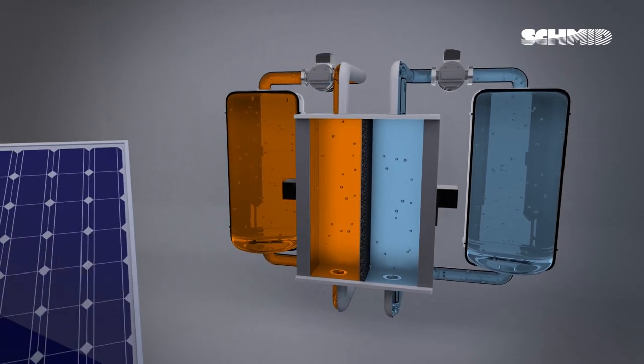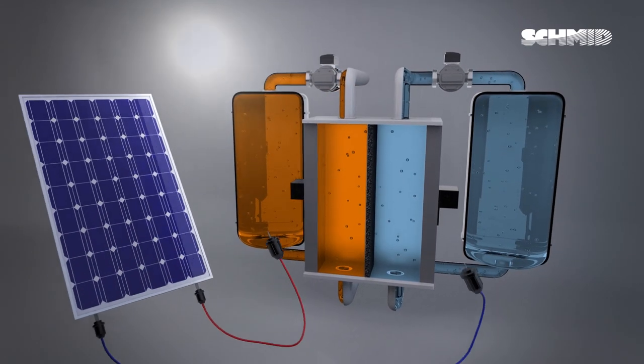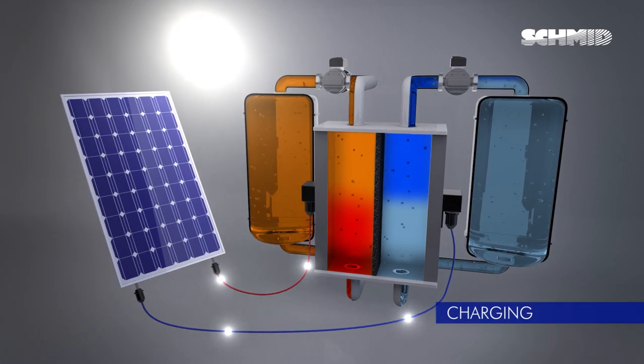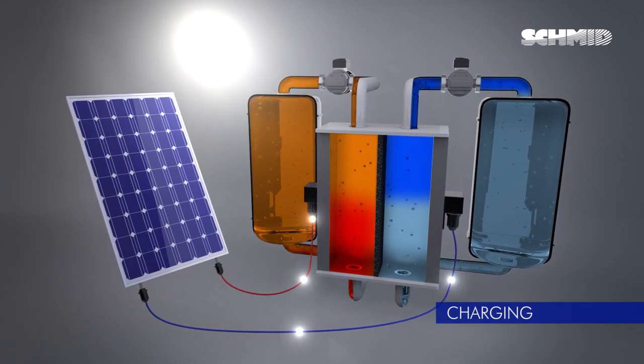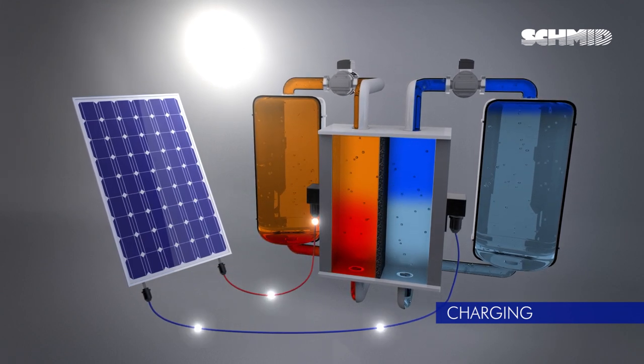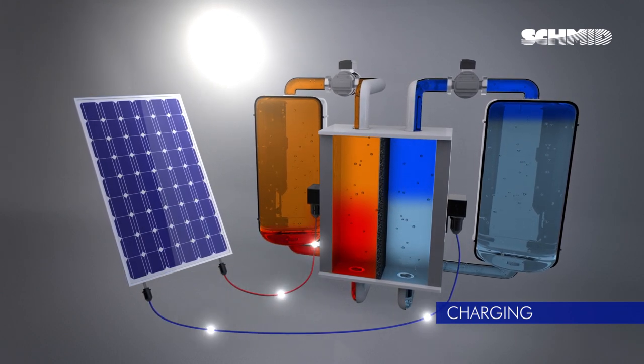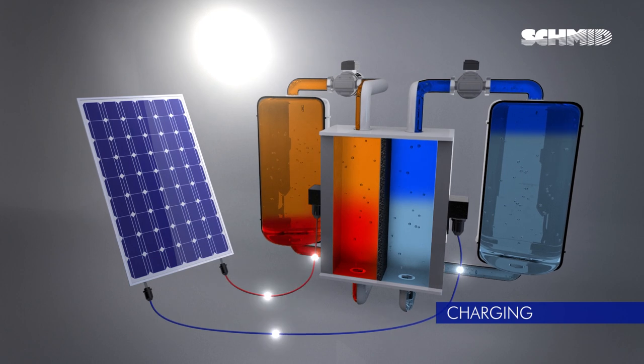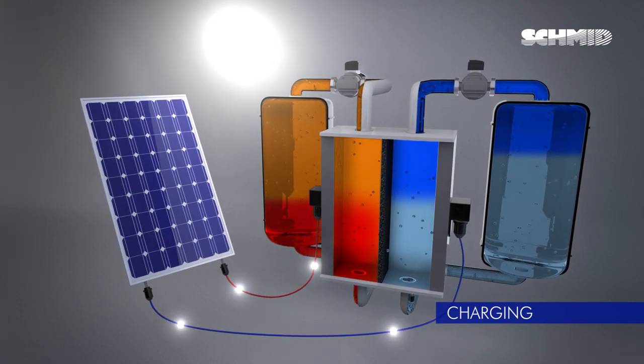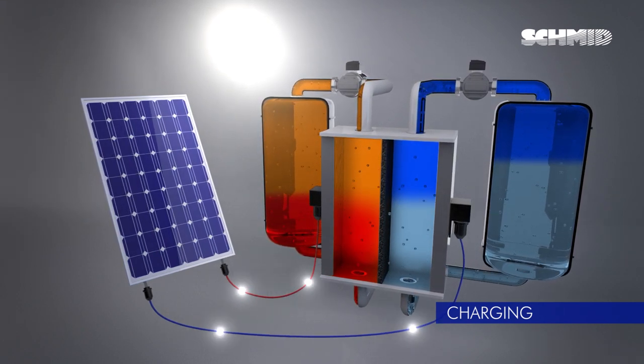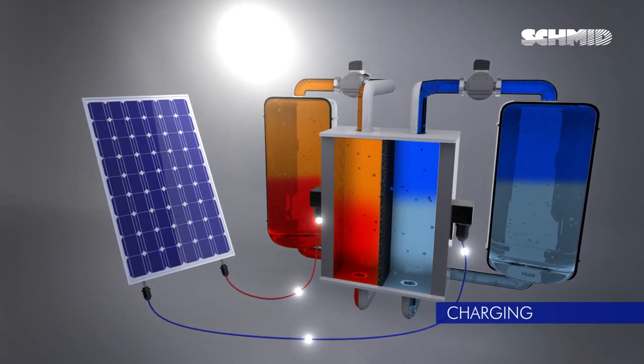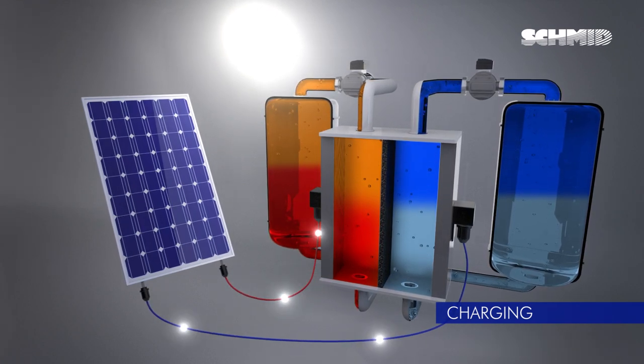An external electrical power source like a PV installation supplies the energy to charge the vanadium redox flow battery. The two vanadium electrolytes are flown through the cell stack in which the electrical energy is converted to chemical energy. The electrolytes charged within the cell are flown back to the tanks, increasing the battery's state of charge.